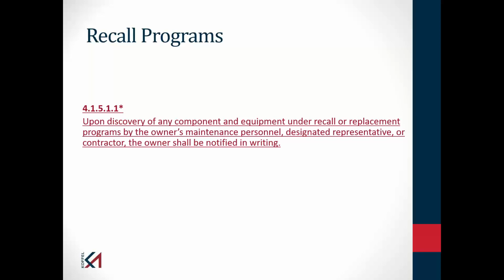So the way I might do this is, because sometimes I can't see it from the floor when I look at the sprinkler, I don't know well enough. But when I go look at your spare sprinkler cabinet and I look at those sprinkler identification numbers, I can do a search and I can determine if that sprinkler is subject to recall. And since you should have sprinklers in your spare sprinkler cabinet that are representative of the sprinklers in the building, that's probably the best way to do that. But the language doesn't quite say the contractor has to do what I just said. It says if the contractor happens to notice that you have recalled sprinklers.